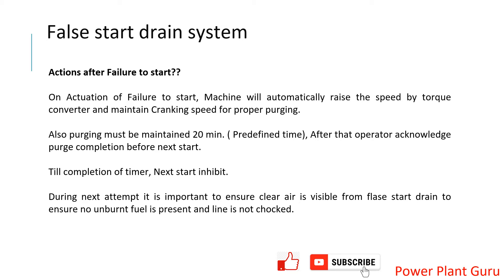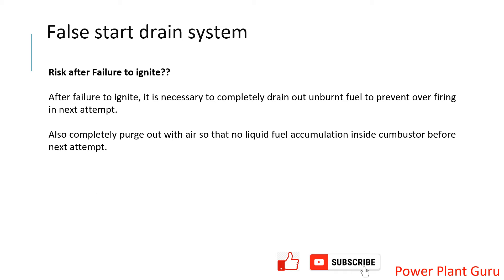During this time there are different drains — essentially three drains. From those drains you will see air coming when the RPM of the machine is low. Air will start coming and slowly that air will bring the fuel along with it from different areas of your turbine, which may be the combustion area, exhaust area, or in between. You can check whether air is coming from those three different false start drains.